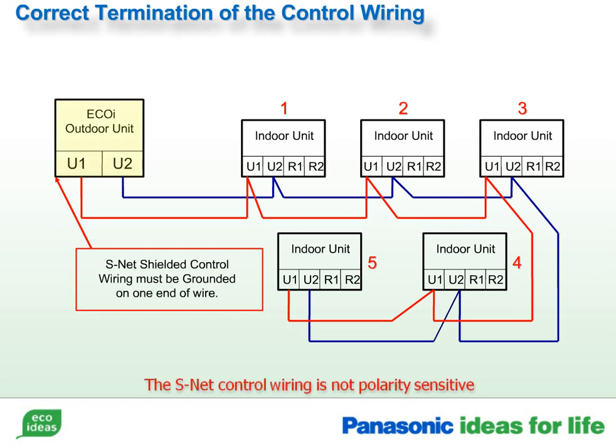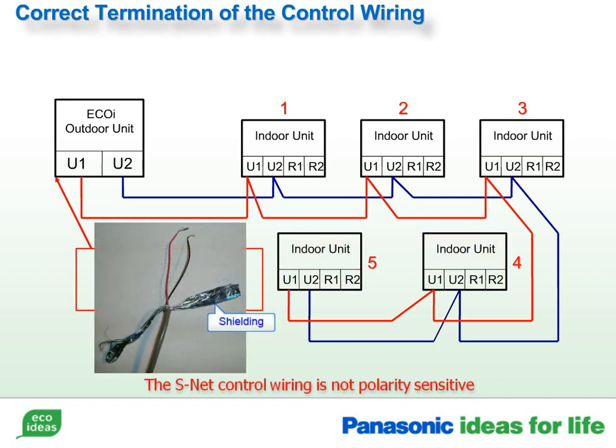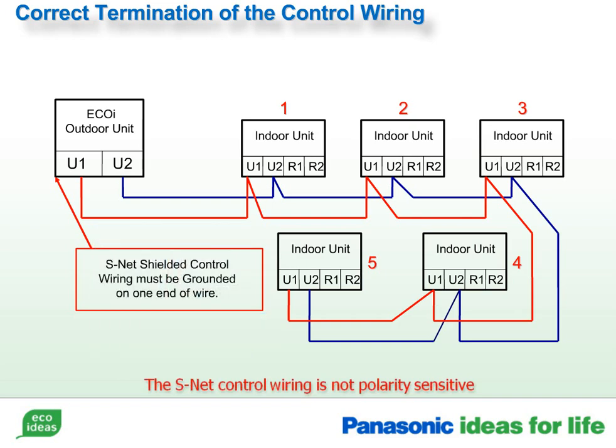Starting at U1 and U2 of the outdoor unit, connect the first indoor unit to U1 and U2. Continue this daisy chain method and connect to each indoor unit. Twist the shielding of your control wire together at each indoor unit, but only connect it at the condenser. The U1 and U2 control wiring is also referred to as the S-net. The S-net control wiring is not polarity sensitive.